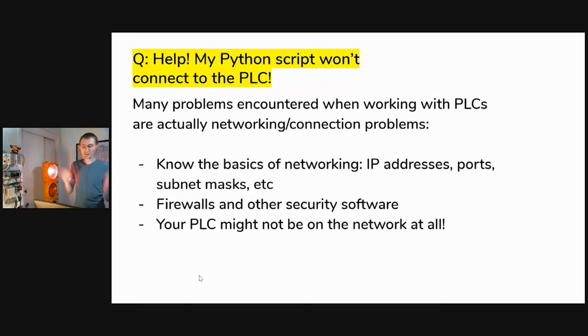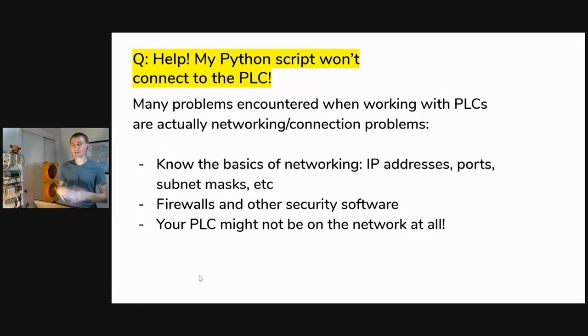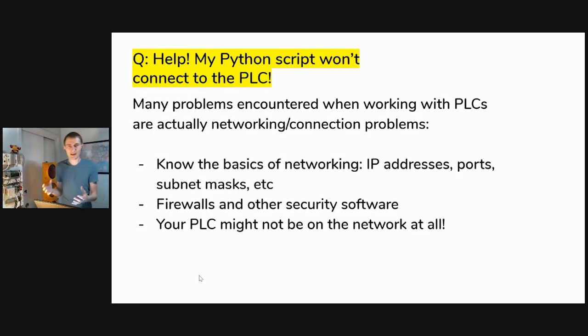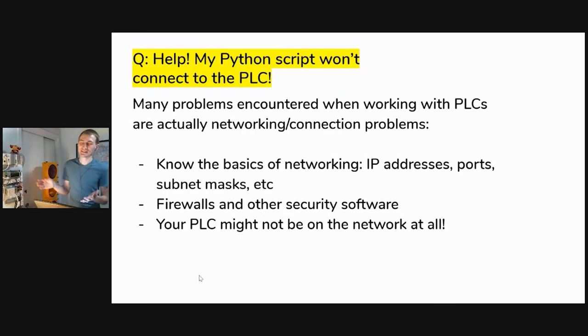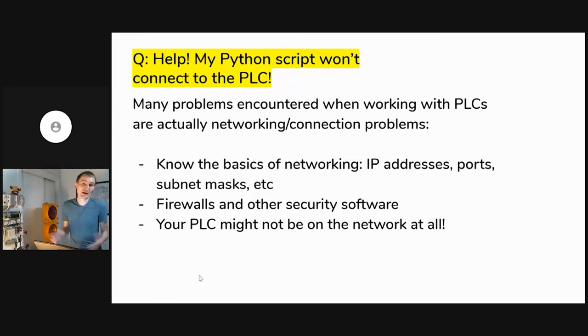Another common issue: my Python script won't connect to the PLC. Many problems you encounter when working with PLCs aren't actually PLC problems — they're networking problems. Make sure you know all the IP addresses involved, the port numbers for the protocols you're using, how subnet masks work, and what firewalls are installed. Also keep in mind that many PLCs are kept off the internet and even off the office network to protect them from hackers. A PLC might be plugged into the same switch as your laptop but the switch may be configured to block that traffic — so understand your networking situation before sending commands.